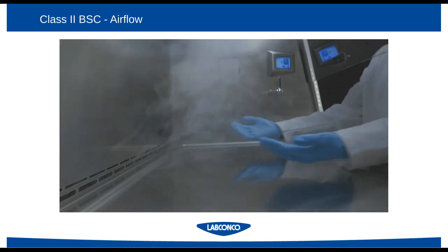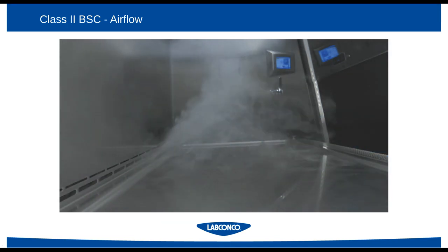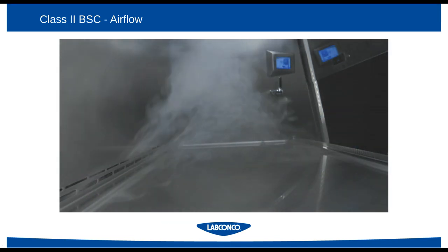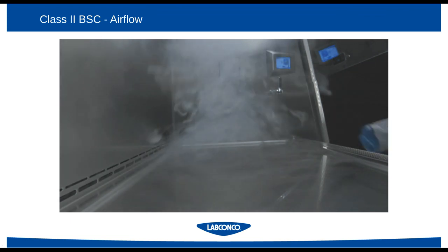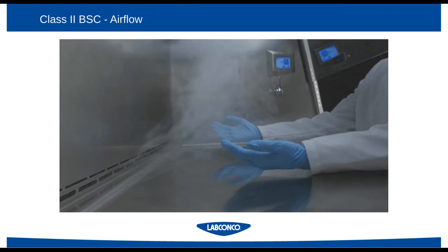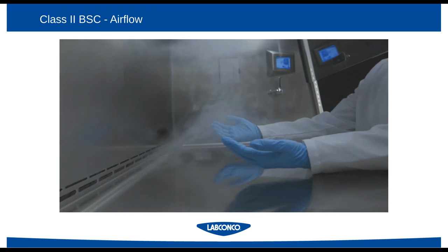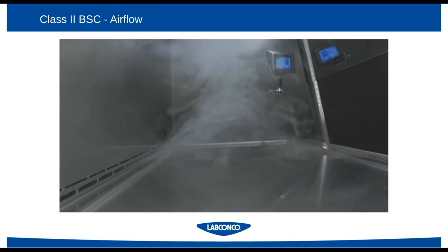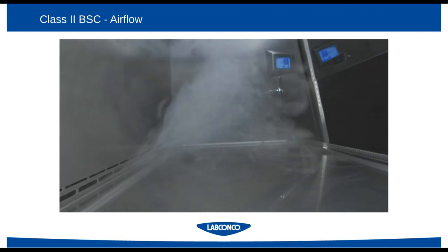So as you can see with a user's hands in there, the laminar flow is not heavily disrupted, but if you take up that space with a large instrument or large materials, it can readily disrupt that airflow and restrict its pathway to the vents, which means that it can cause turbulence, and that may impact the samples, or worse, potentially impact the safety of the user.